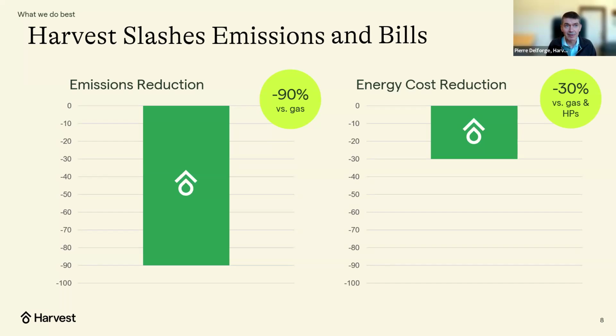So the load shifting that I mentioned early on is really what helped us achieve higher efficiency, because we run the heat pump when it's warmest. As you know, the heat pump is more efficient when it's warmer outside, versus typical heat pumps that will run when it's coldest, because that's when people need the most heat. So there can be a temperature difference of up to 20 degrees, typically between early morning and the middle of the day. And that's worth about 100% efficiency for heat pumps. So typically 1 point of COP higher by running the heat pump when it's warmer rather than when it's coldest. You avoid defrost, you avoid a lot of issues that impact heat pump efficiency.